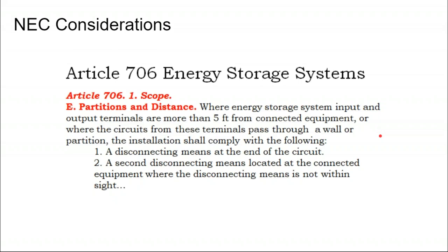When output terminals are more than 5 feet from the equipment, or where the terminals pass through a wall, they need to have a disconnecting means for the battery at the end of the circuit. And then a second disconnecting means if the equipment is not within sight.